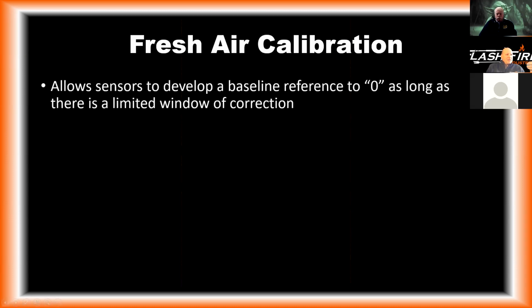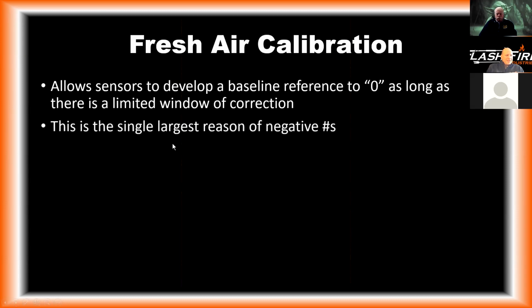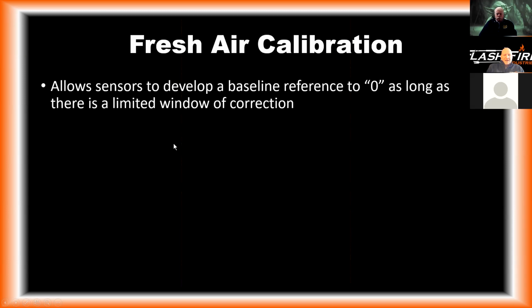What it does is it allows sensors to develop a baseline reference to 0 as long as there's a limited window of correction. So what does that mean? If I have negative 2 parts per million, and I'm standing outside in the fresh air, my fresh air calibration should bring all of that back to 0. What it doesn't mean is if I'm reading 300 parts per million and I'm in a fresh air environment and I try to fresh air calibrate it, the meter's going to say, whoa, there's something else going on. You need to calibrate this meter.